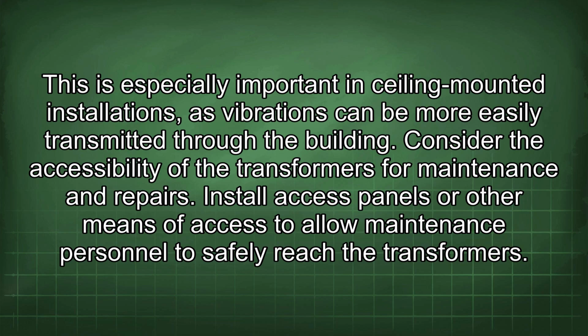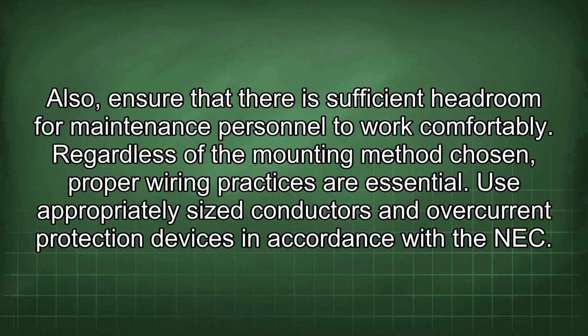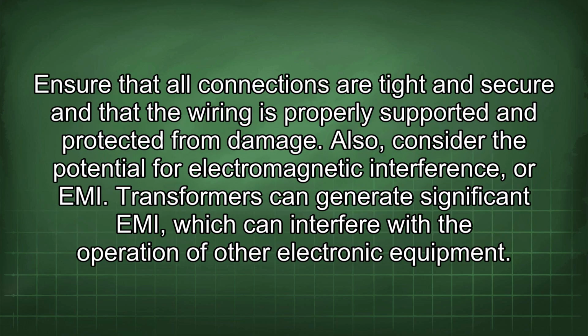Consider the accessibility of the transformers for maintenance and repairs. Install access panels or other means of access to allow maintenance personnel to safely reach the transformers. Also, ensure that there is sufficient headroom for maintenance personnel to work comfortably. Regardless of the mounting method chosen, proper wiring practices are essential. Use appropriately sized conductors and overcurrent protection devices in accordance with the NEC. Ensure that all connections are tight and secure and that the wiring is properly supported and protected from damage.